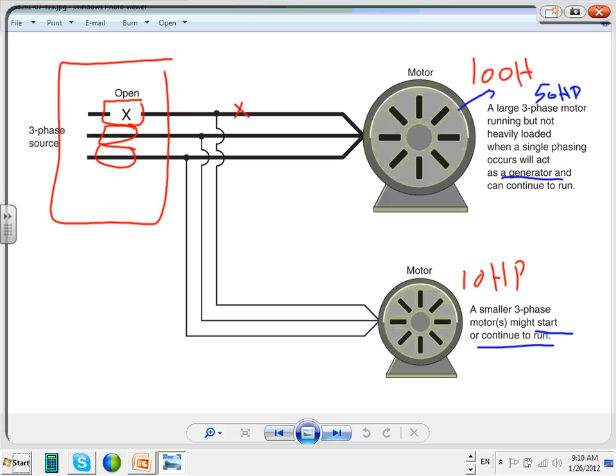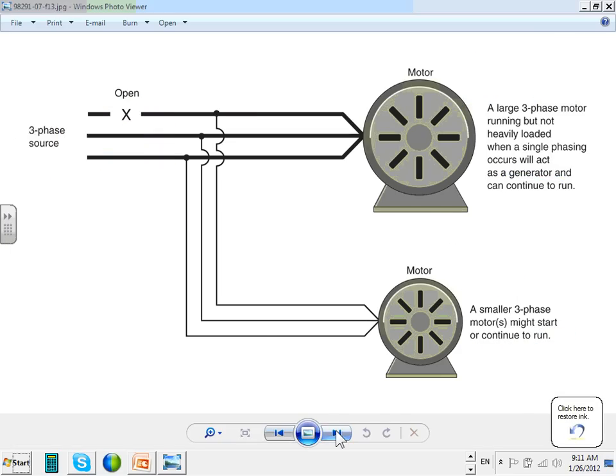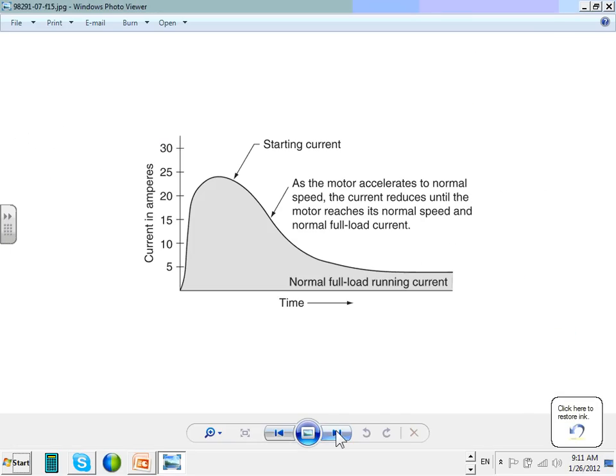If that stops, the big boy, you can't start it when you lose a phase. But if it was running, it could, on lightly loaded, say 50% or less, 30% of it loaded, it continued to run. Any comments, guys? Any questions? The reason why we focus a lot on motors is because every machine that we put in our equipment has some type of motor in it. So single phasing, in the book they say, can create a lot of issues.